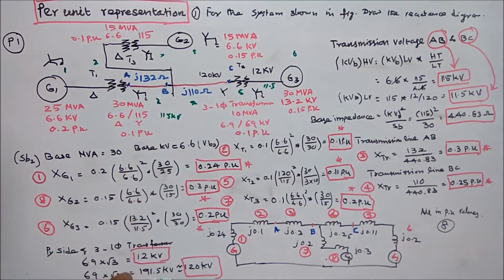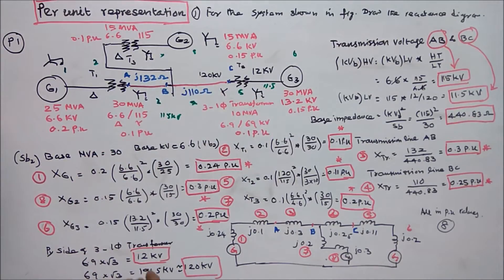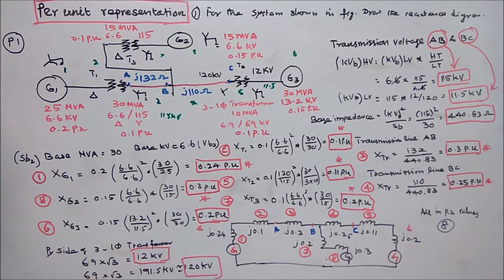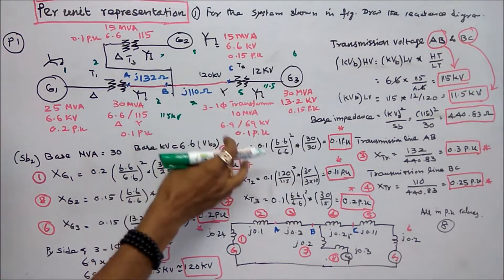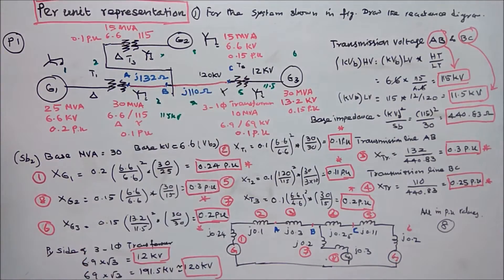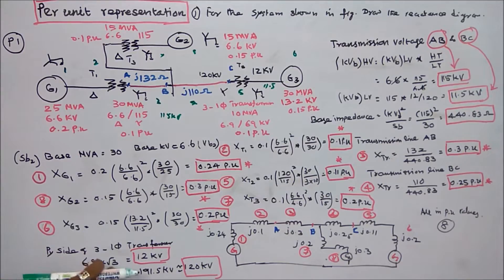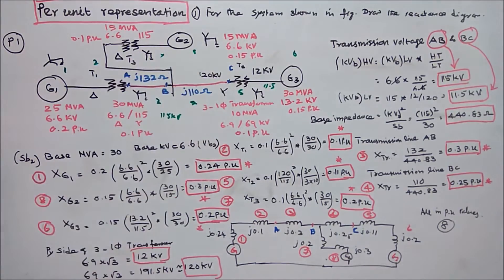Fifth is a transformer made of three single-phase transformers. So 3 into 10 equals 30 MVA. Voltage is 6.9/69 kV. Both sides are star connected. In star connection, line voltage equals root 3 times phase voltage. Therefore 69 into root 3 equals approximately 12 kV.